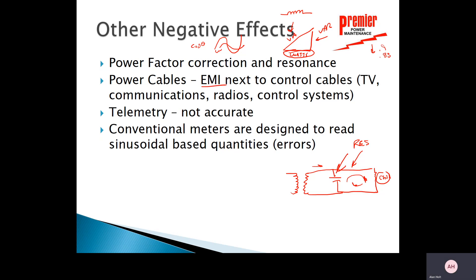Other negative effects include electromagnetic interference from power cables to nearby control, communications, TV, or radio cables. Telemetry for reading watts, vars, power factor, voltage, and current may not be accurate unless true RMS metering is used. Conventional meters are designed to read sinusoidal quantities, so non-sinusoidal waveforms will produce measurement errors.